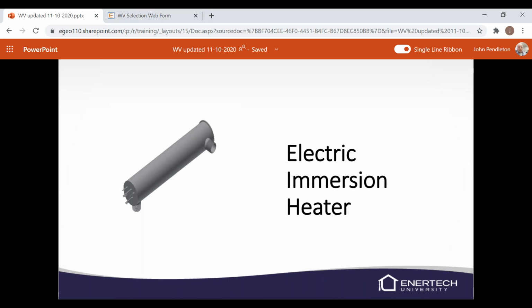This is the electric immersion heater. If for some reason it leaks, there are some unions that are threaded onto it, and so you can get it out of the system if you need to. The only reason I would think that one of these would fail is if you ran it without water flow.